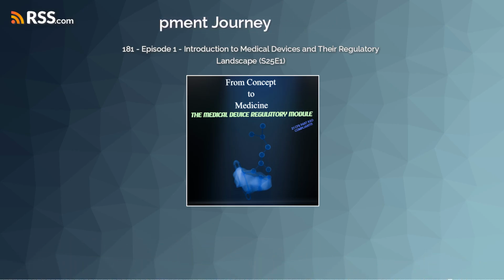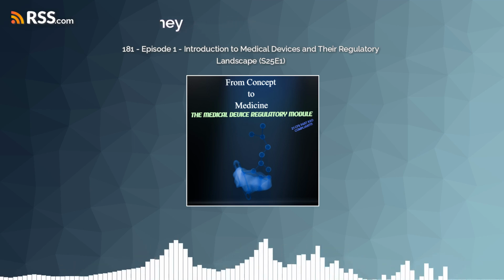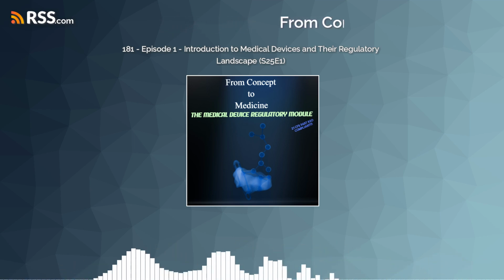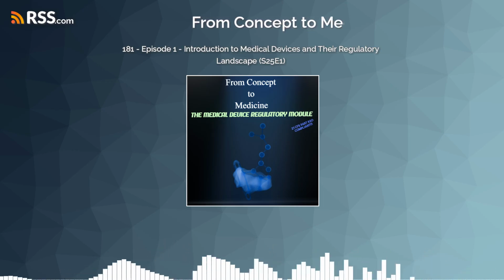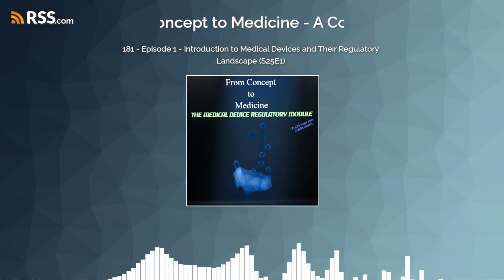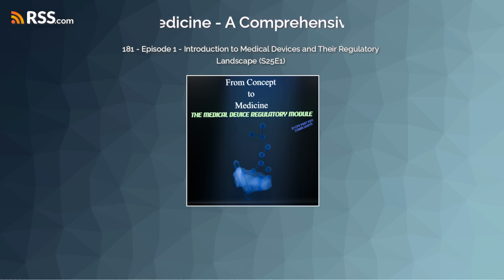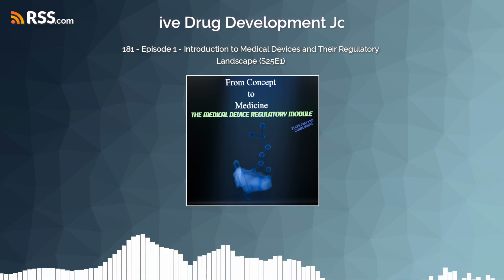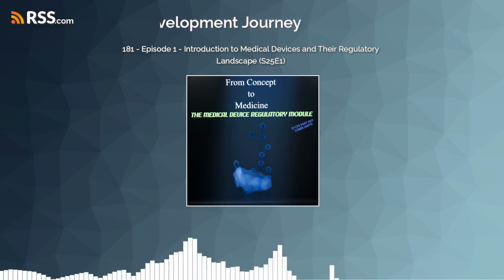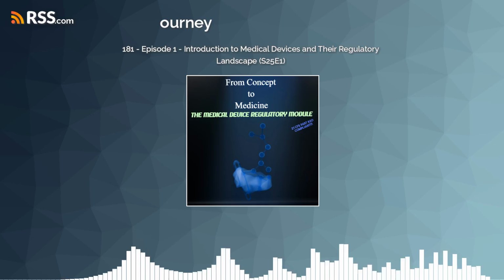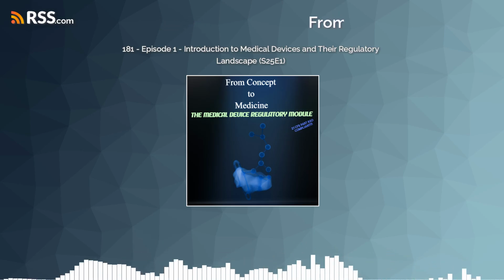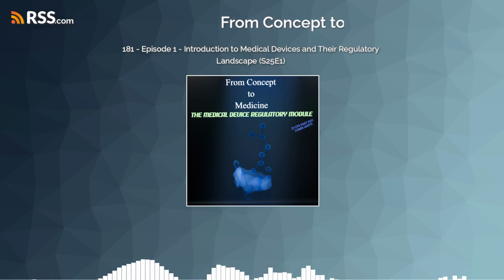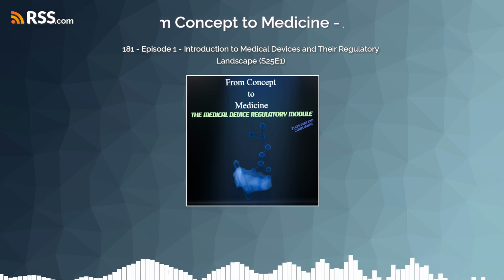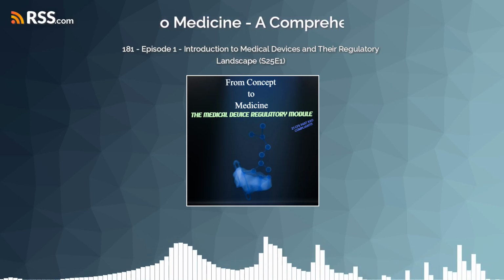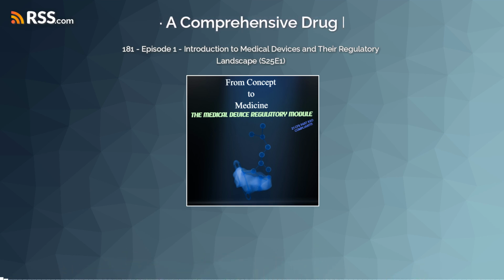A continuous loop. Okay, so let's start at the bottom then. The lowest risk category. What is that and what does it mean for manufacturers? That would be Class 1. These devices pose the lowest potential risk to patients. They're subject to what the FDA calls general controls. General controls. Okay, what does that mean practically? These are the basic regulatory requirements applicable to all medical devices. Things like registering your establishment, listing your devices, proper labeling, and adhering to the quality system regulation, though with some exceptions.